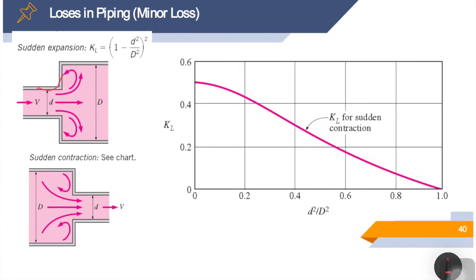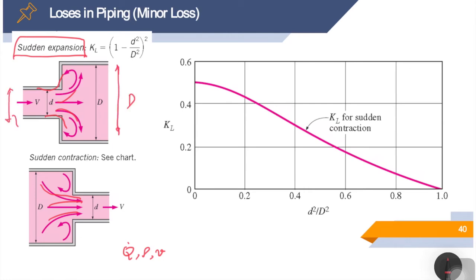Piping systems often involve sudden or gradual expansion or contraction to accommodate changes in flow rate or to control velocity and density. Losses are usually much greater in the case of sudden expansion or contraction due to flow separation. By combining equations of mass, momentum, and energy balance, the loss coefficient for sudden expansion is KL equals (1 minus (small d / large D) squared) squared. An alternative formula given in the book is KL equals alpha times (1 minus A-small over A-large) squared, where alpha is the kinetic energy correction factor.